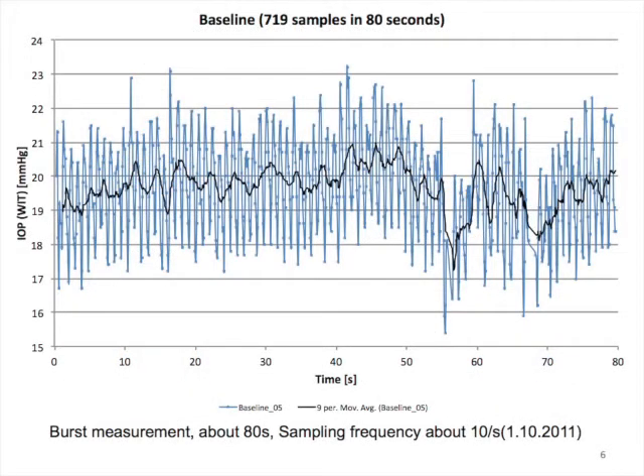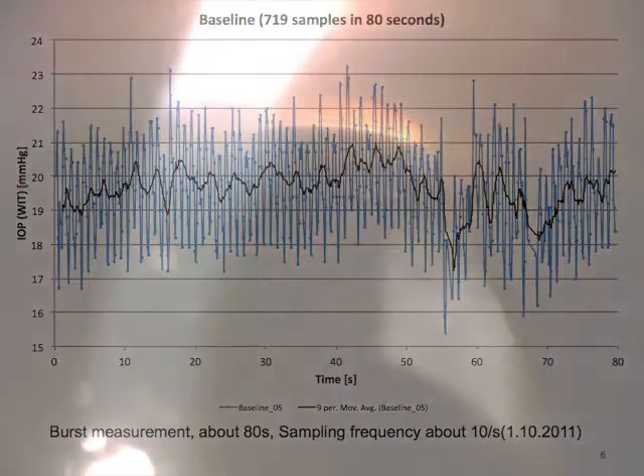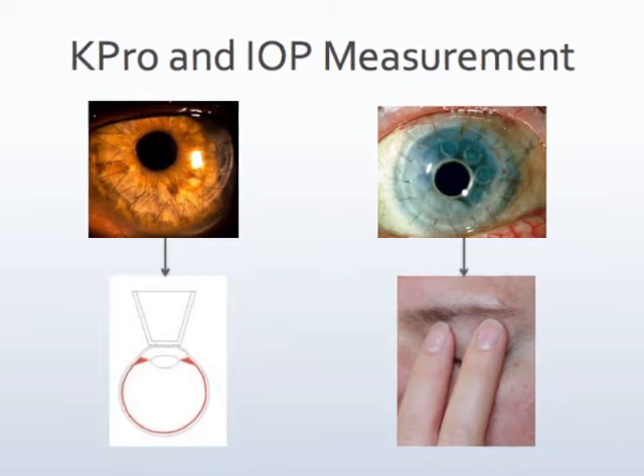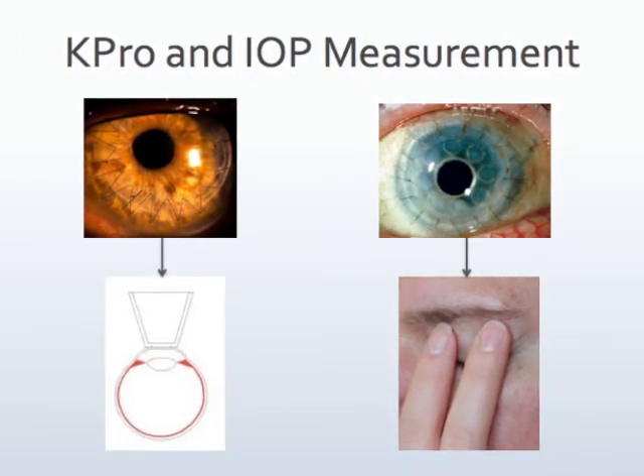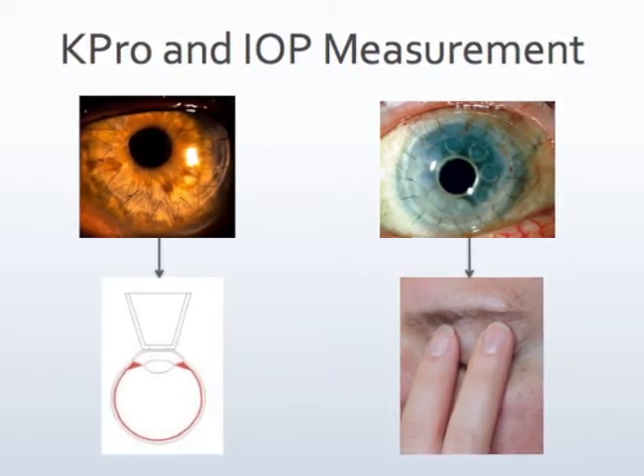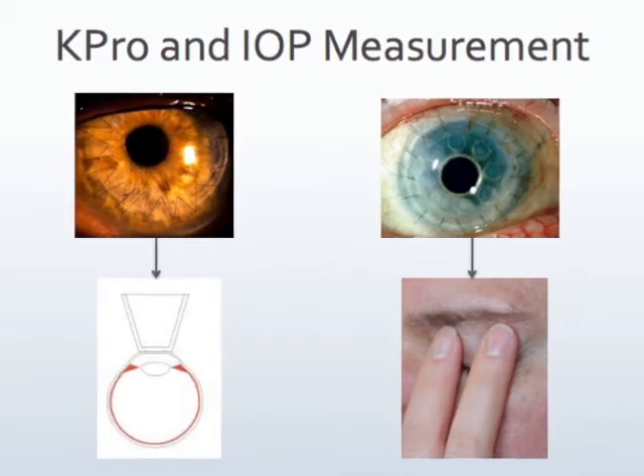Here's an example of a continuous IOP measurement curve where the device was able to collect up to 10 IOP samples per second. The patient was followed for 20 months without signs of intraocular problems so far. Another intended use of the device is IOP measurement in keratoprosthesis patients where finger palpation is the only way to assess pressure.